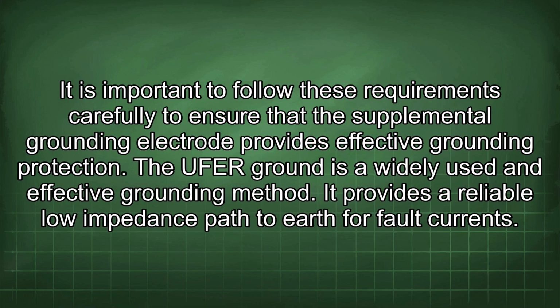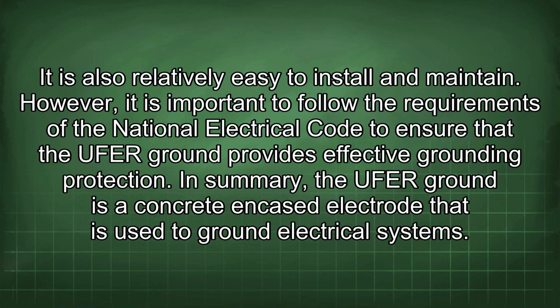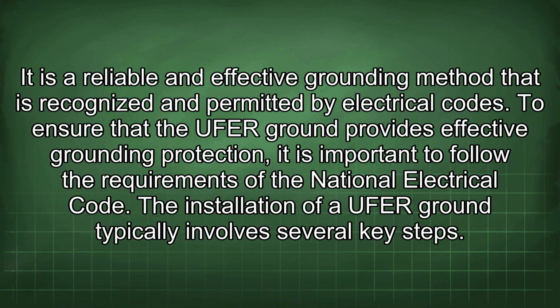The UFER ground is a widely used and effective grounding method. It provides a reliable low-impedance path to earth for fault currents. It is also relatively easy to install and maintain. However, it is important to follow the requirements of the National Electrical Code to ensure that the UFER ground provides effective grounding protection. In summary, the UFER ground is a concrete encased electrode that is used to ground electrical systems. It is a reliable and effective grounding method that is recognized and permitted by electrical codes.